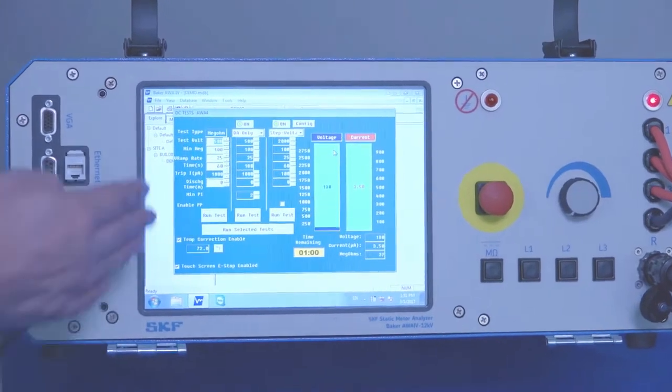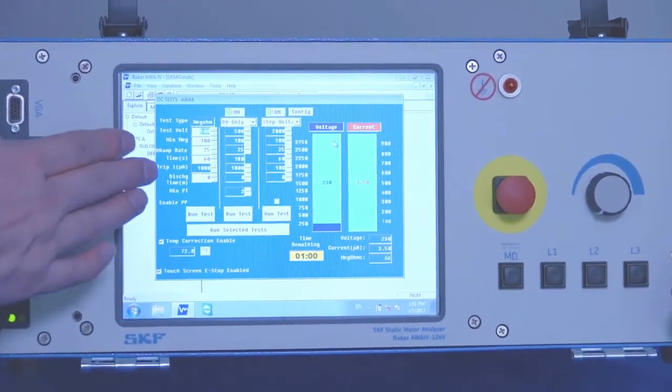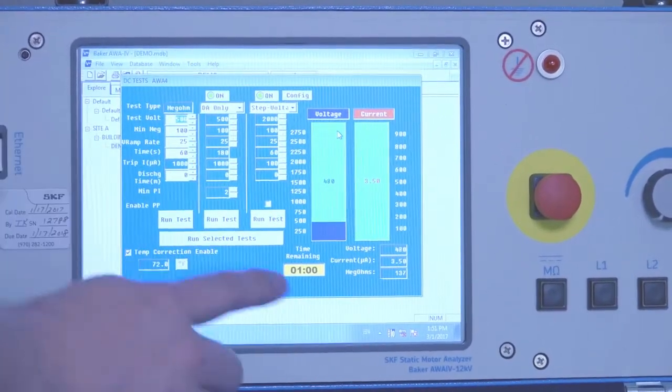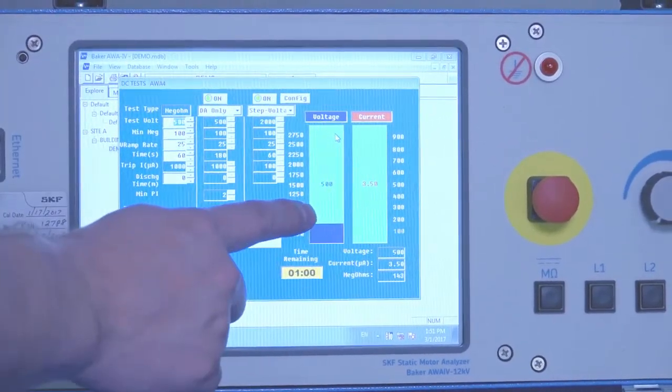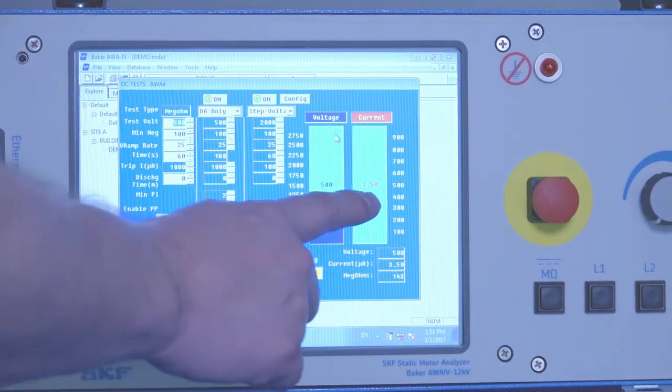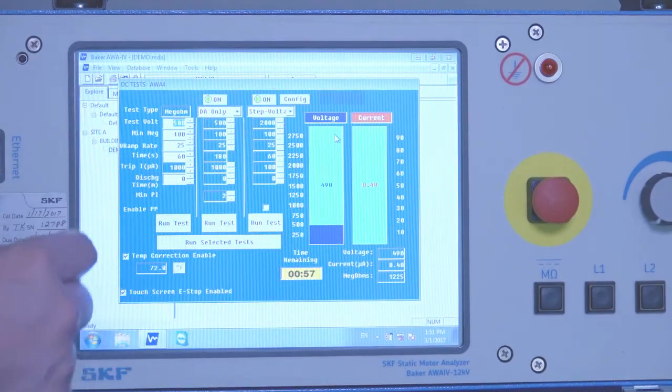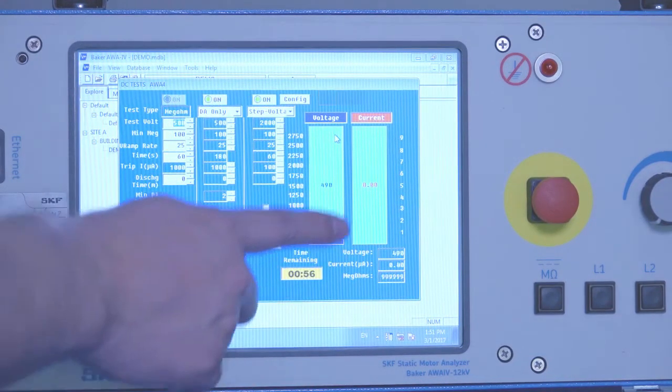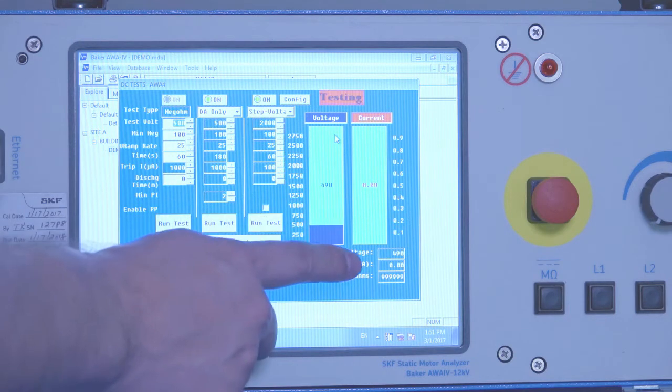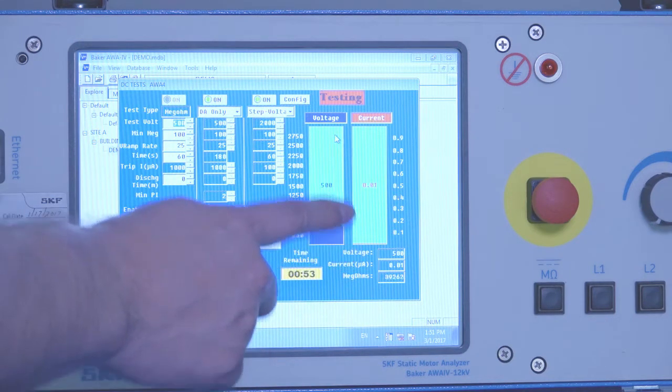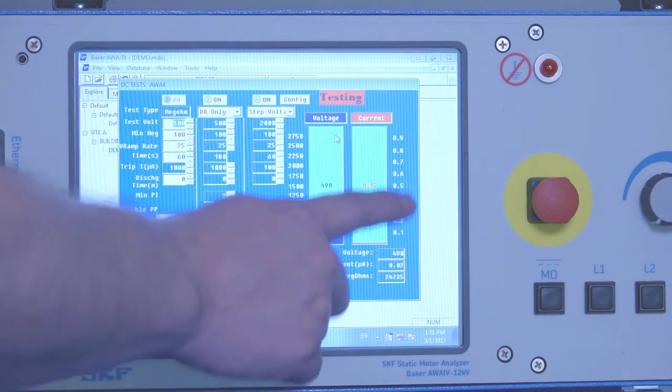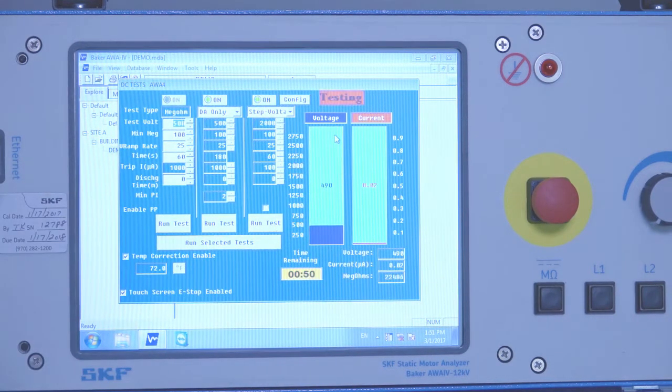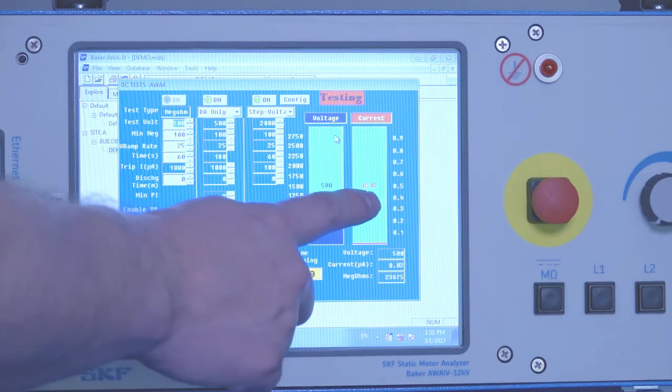And so it's going to proceed through the test order. In this case, it's doing a Megohm test up to 500 volts. We see the higher charging current, which was 3.5 microamps. Now the current is scaling down to measure more accurately the small leakage current, which in this case is 0.02.